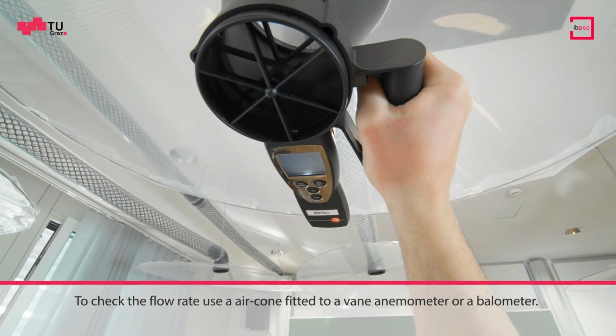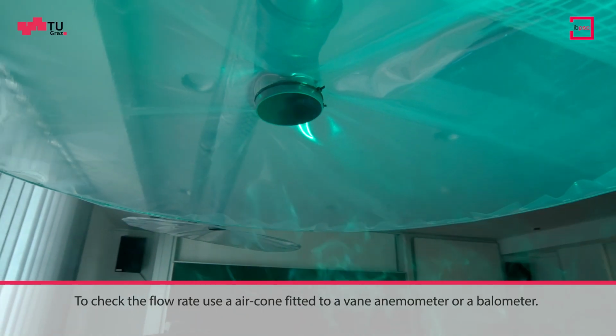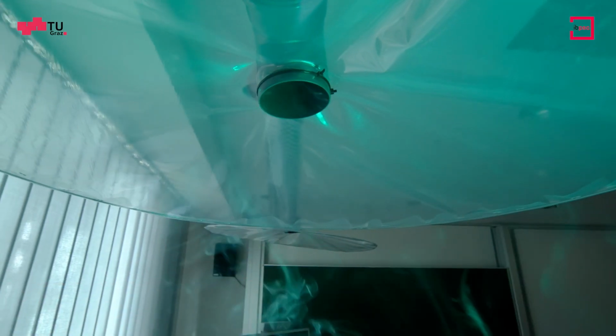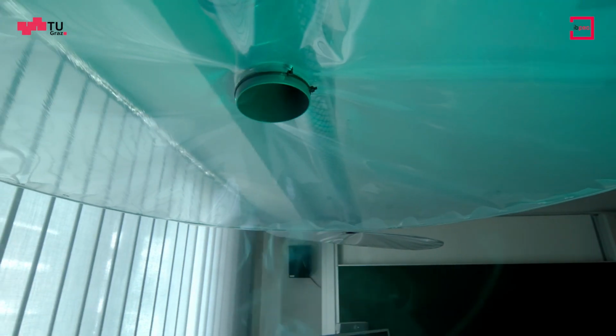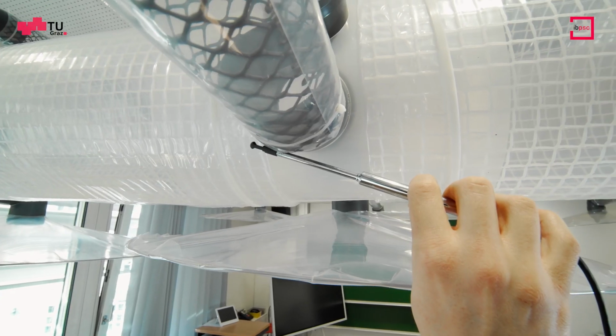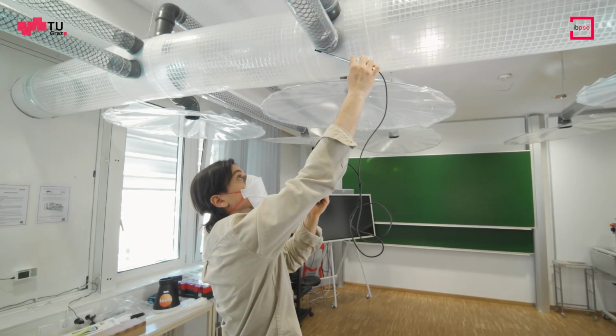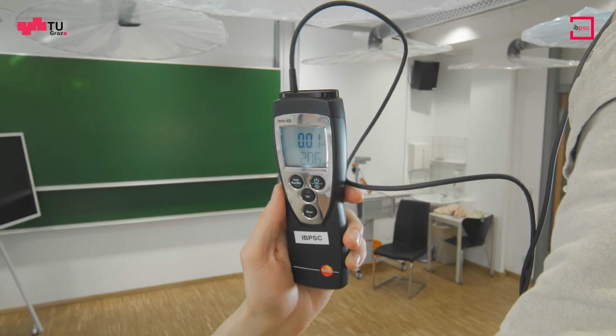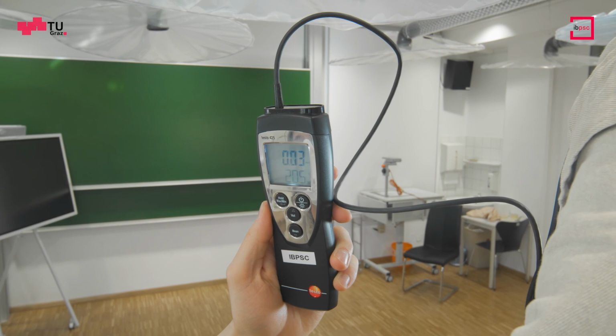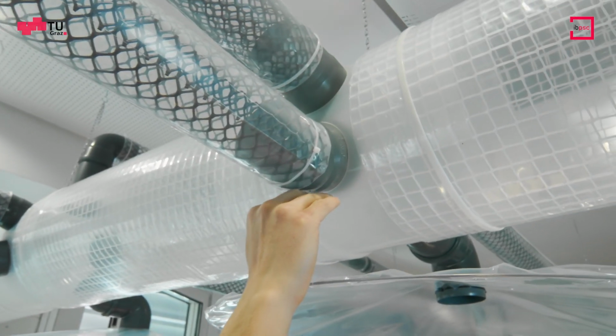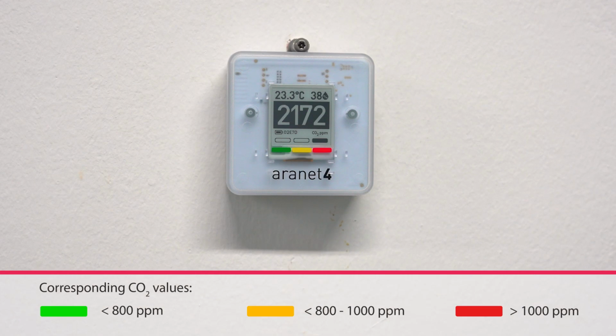Quality assurance is important to ensure that the system is operating correctly. Here we make a quick visual inspection and leakage audit to check that air is flowing correctly through the ducts and there are no unwanted leaks in the system which could cause pressure drops. You can use a thermal anemometer to see whether air is leaking at any of the connections around the fan or at any of the ductwork connection points. Alternatively, you can also use the back of your hand to feel for any drafts or airflows around any of these points which could indicate an air leak which needs attention.